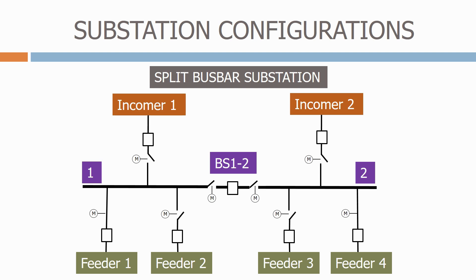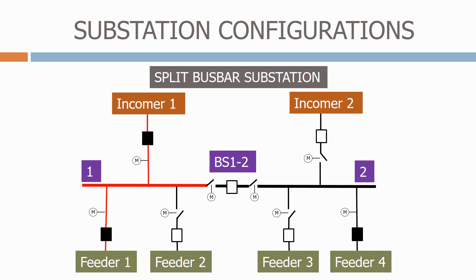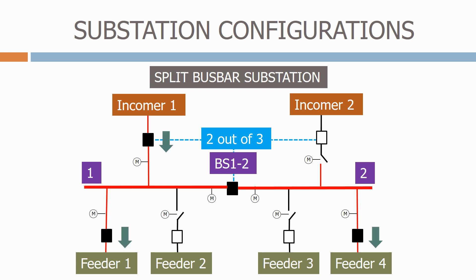One solution is a split bus bar substation. To give more security we add another incomer as an alternative source of supply, and a bus section circuit breaker so that if one bus bar is out of service we can still supply some of the feeders. The normal configuration when both incomers are available is for each incomer to feed its own bus bar with the bus section breaker open. If we lose one incomer, we close the bus section isolators before closing the bus section circuit breaker to energise the dead bus bar. This arrangement is also called a 2-out-of-3 system, where the normal operation is to have two of the three circuit breakers closed at any one time.